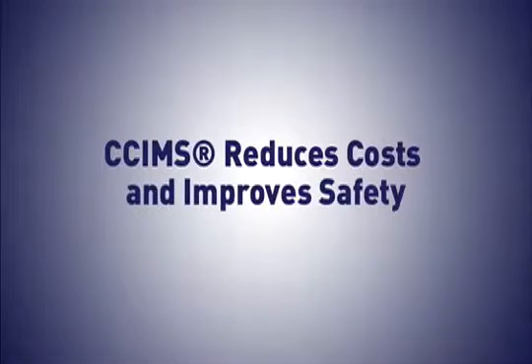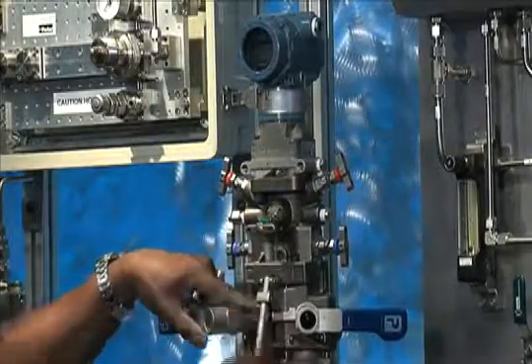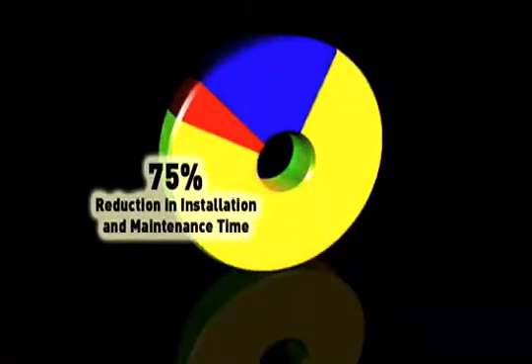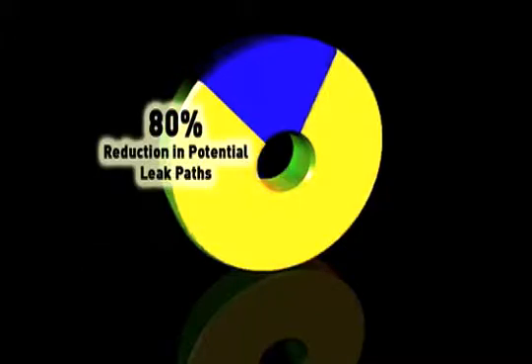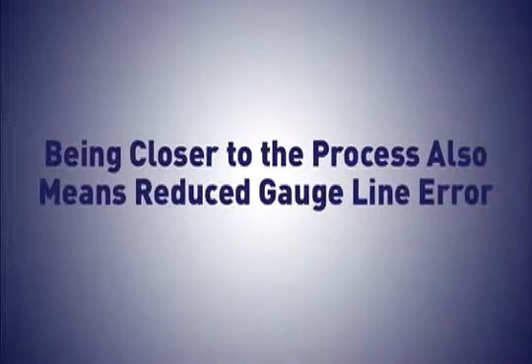CCIMS reduces costs and improves safety. It changes process control by close coupling instruments to the process pipe. The result? A 75% reduction in installation and maintenance time. And with dramatically fewer joints, there is an 80% reduction in potential leak points. Being closer to the process also means reduced gauge line error.